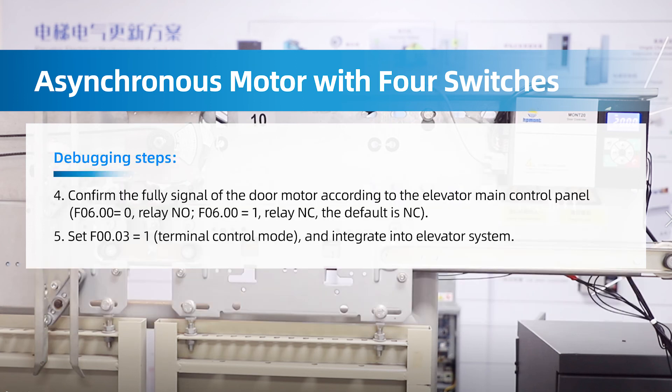Step 4: Confirm the full-open signal of the door motor according to the elevator main control panel. F06.00 equals 0 for relay NO; F06.00 equals 1 for relay NC — the default is NC. Step 5: Set F00.03 equals 1 and integrate into the elevator system.